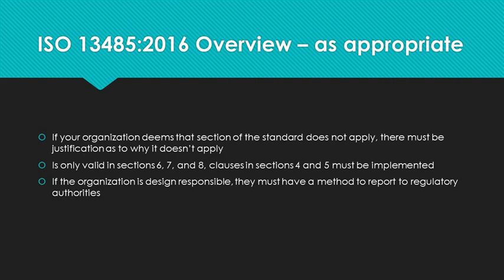Throughout ISO 13485, the phrase 'as appropriate' is used. If your organization deems that a section of the standard does not apply — for example, your product does not have service or installation — you must note that as a justification as to why it does not apply. Usually, you state this in the scope in the quality manual. Not applicable can only be done in clauses in sections 6, 7, and 8. Reporting to regulatory authorities is a clause in section 8. However, if the organization is design responsible, then they must report to regulatory authorities, so that clause cannot be deemed not applicable, even if they are a component manufacturer. All requirements in sections 4 and 5 must be implemented — none of them can be excluded or determined as not applicable.